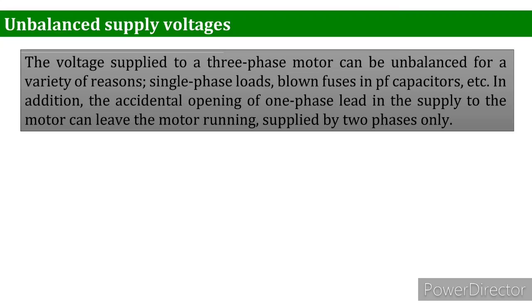Unbalanced supply voltage. The voltages supplied to a three-phase motor can be unbalanced for a variety of reasons, like single-phase loads, blown fuses in power factor correction capacitors. In addition, the accidental opening of one phase lead in the supply to the motor can leave the motor running supplied by two phases only.